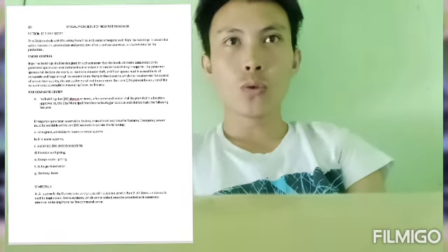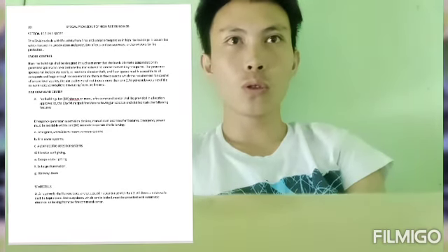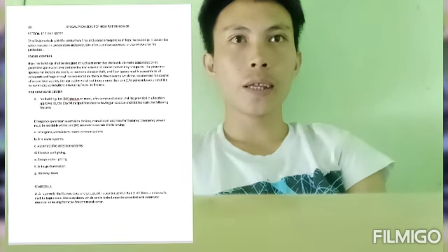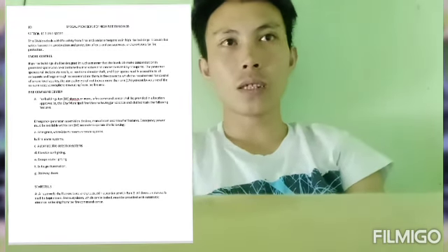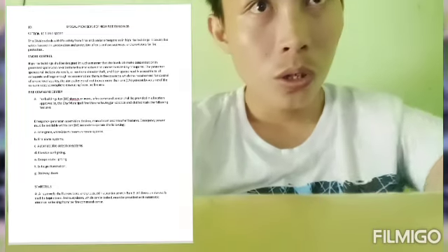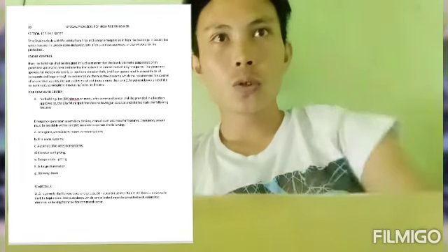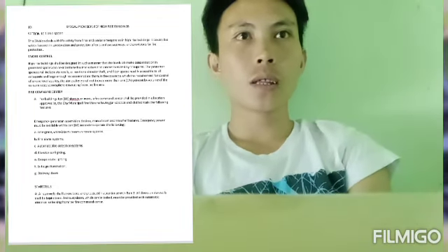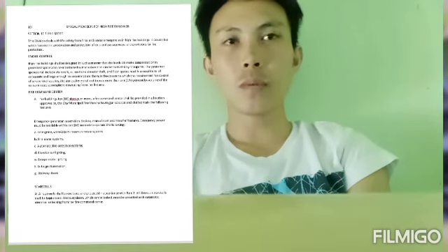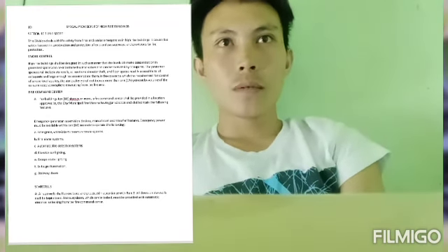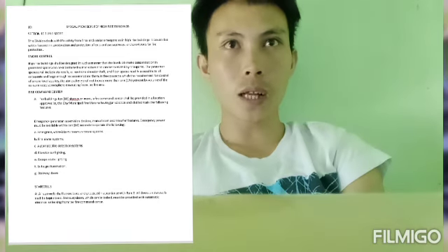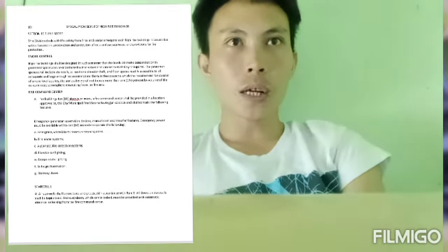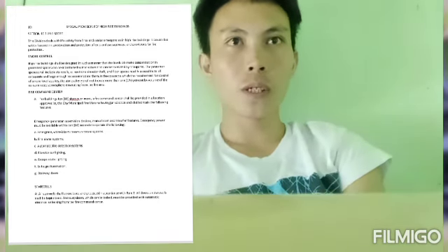Section 10.2.19.2 A high-rise building is one in which the distance between the floor of the topmost story and the ground level is 15 meters or more. Building height shall be measured from the lowest level of fire department vehicle access to the floor of the highest occupiable story.